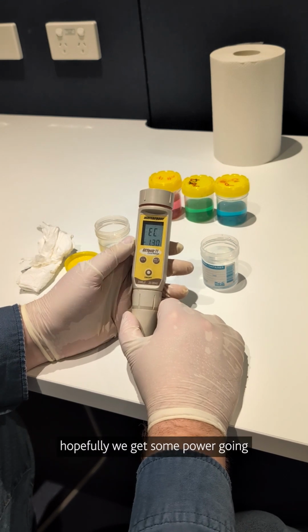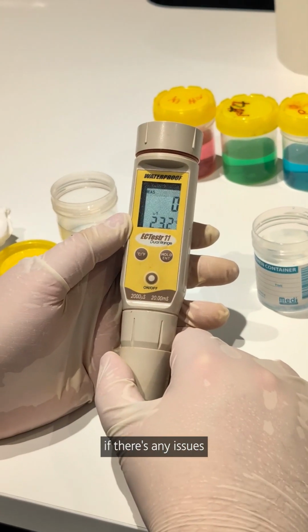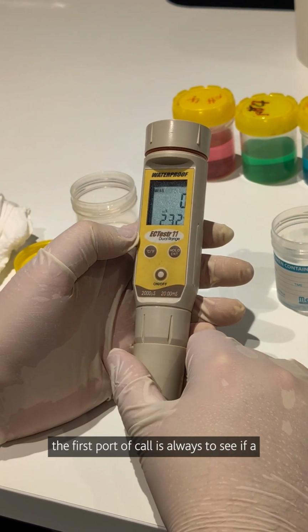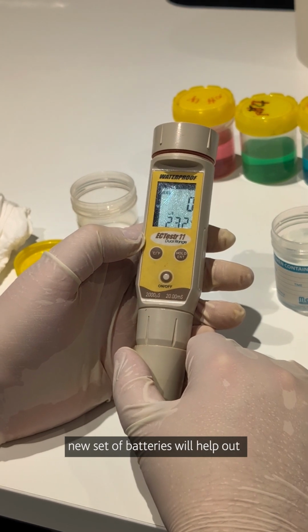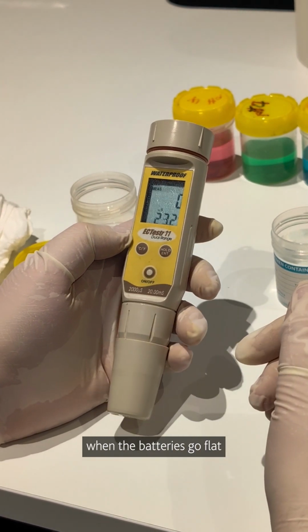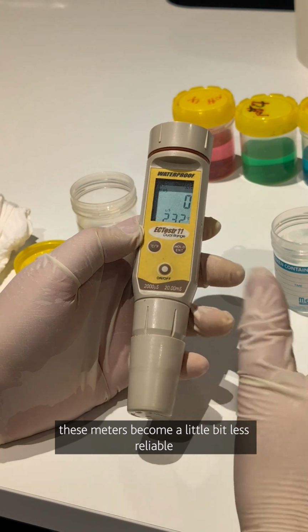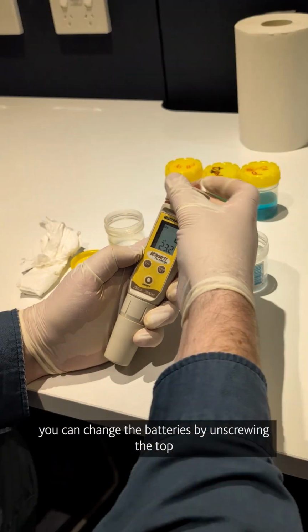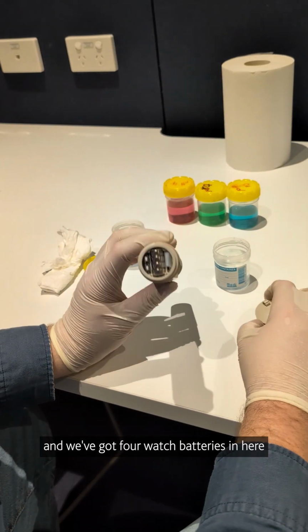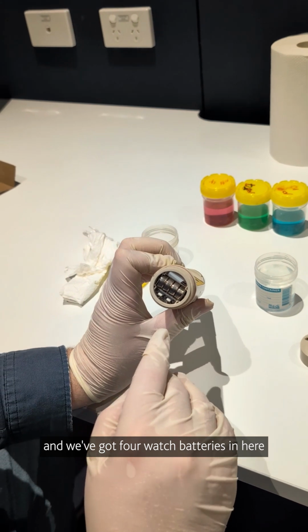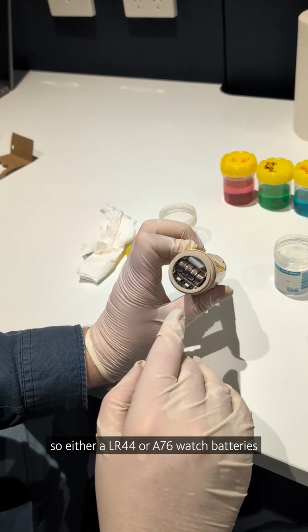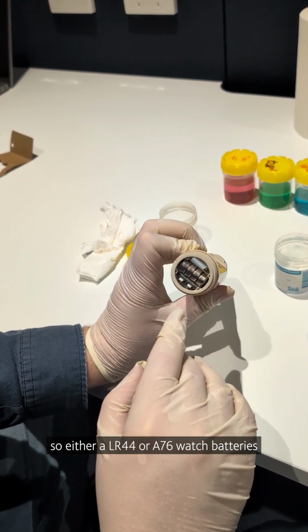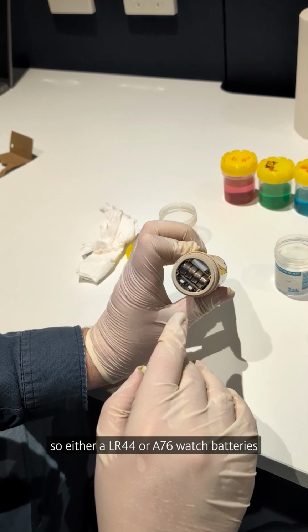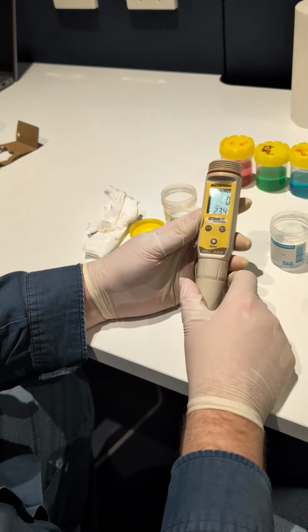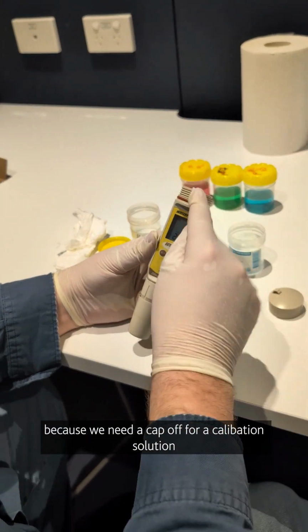And hopefully we get some power going. If there's any issues, the first protocol is always to see if a new set of batteries will help out. When the batteries go flat, these meters become a little bit less reliable. You can change the batteries by unscrewing the top, and we've got 4 watch batteries in here. So either LR44 or A76 watch batteries. And we'll leave the cap off because we need the cap off for a calibration solution.